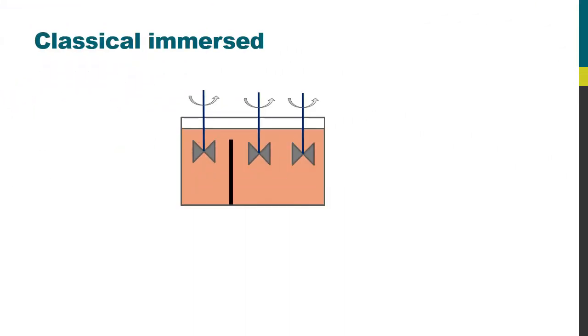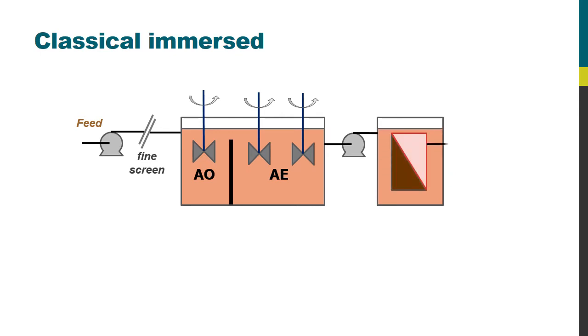So we're back with our immersed MBR, starting with the process tank which has an anoxic and an aerobic zone. The wastewater is fed to the tank via fine screens, normally of one to two millimeter rating, and the sludge from the tank is directed to the membrane tank which is fitted with a membrane from which permeate is extracted.